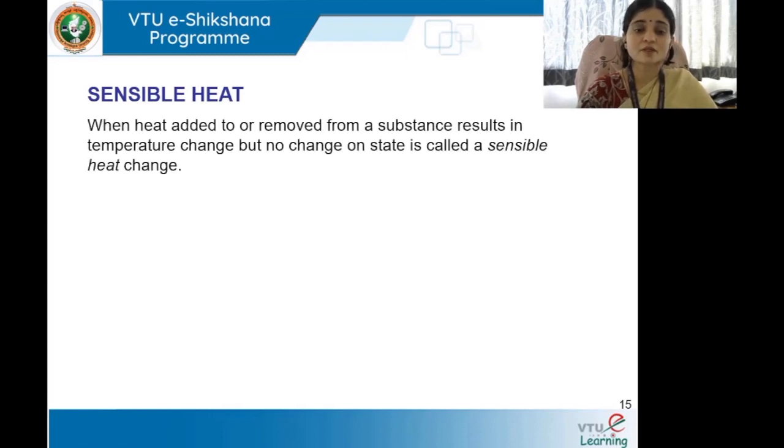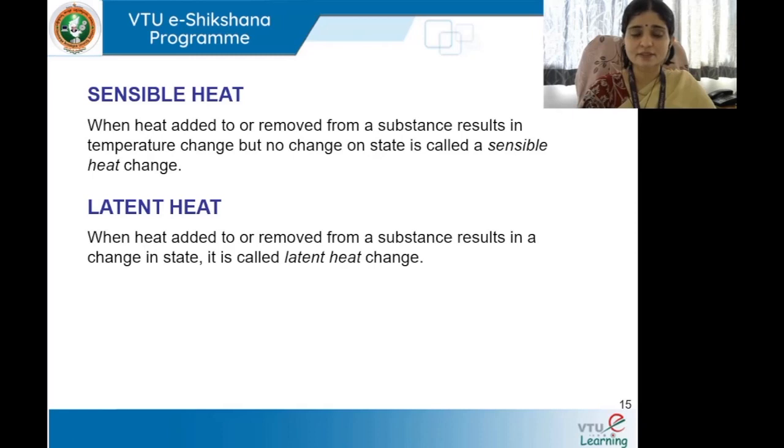Now, the next terminology, sensible heat. When heat added to or removed from a substance results in the temperature change but not a change in the state, it is called a sensible heat change. Okay, so you are adding or removing heat and it only results in the temperature change of the substance but does not affect the state of the substance. Whereas latent heat is when the heat added to or removed from a substance results in a change in state of the substance. That is called a latent heat change.